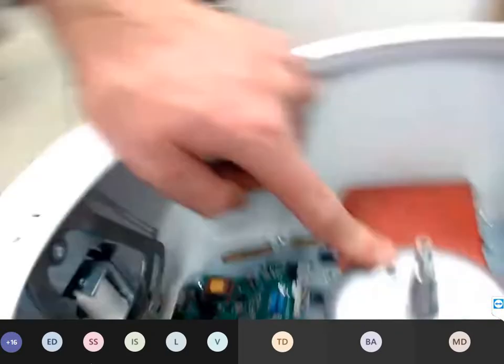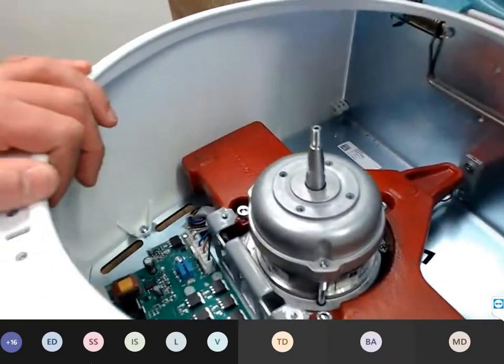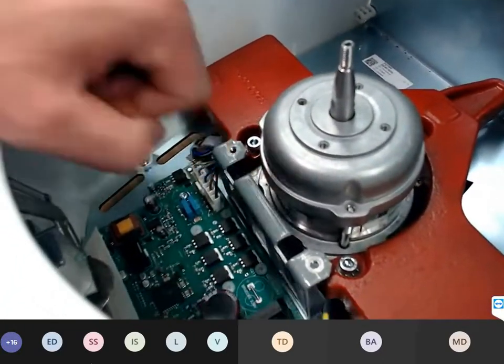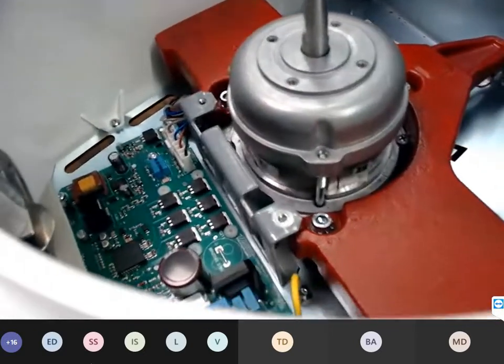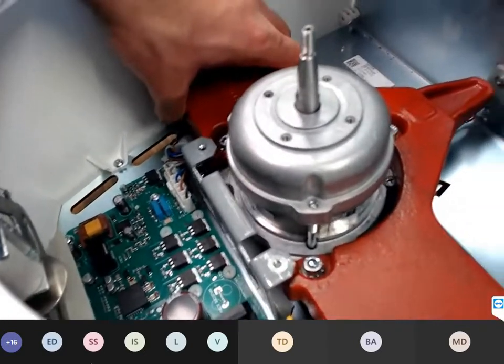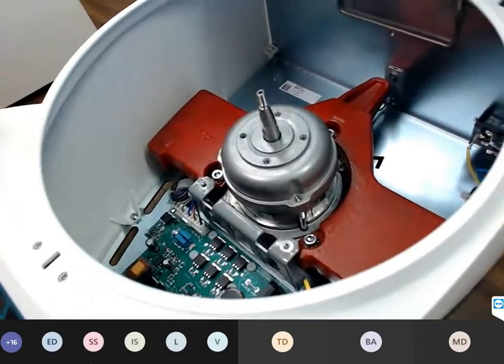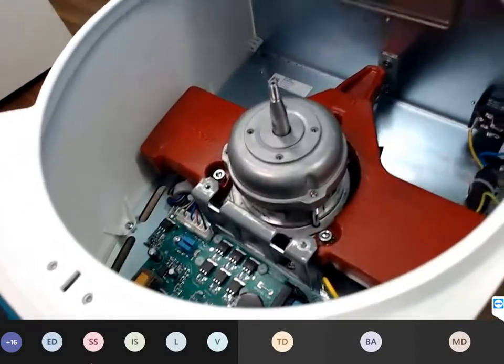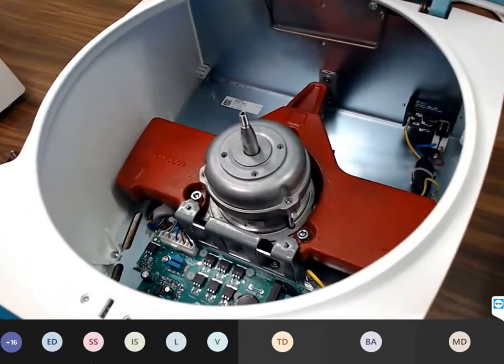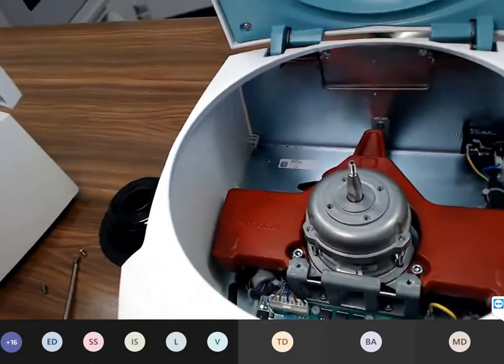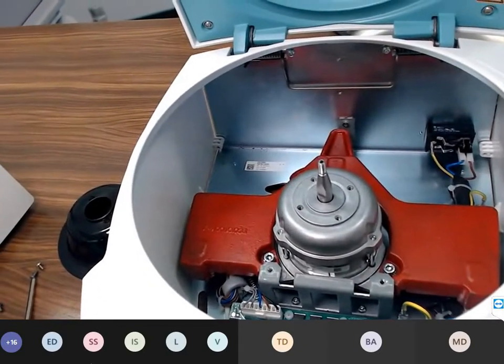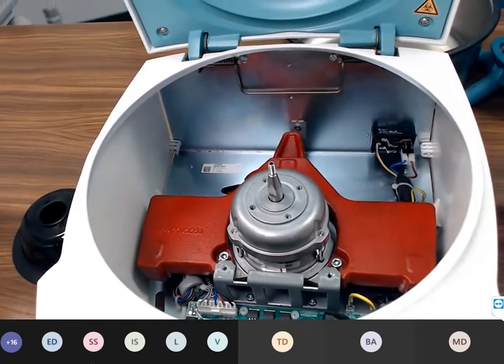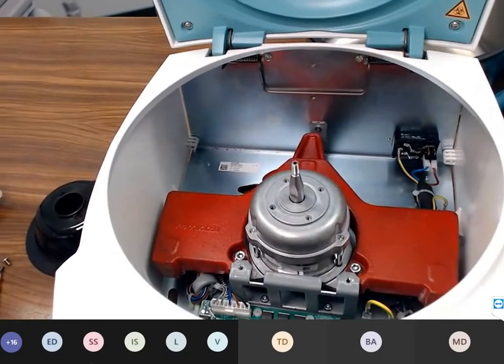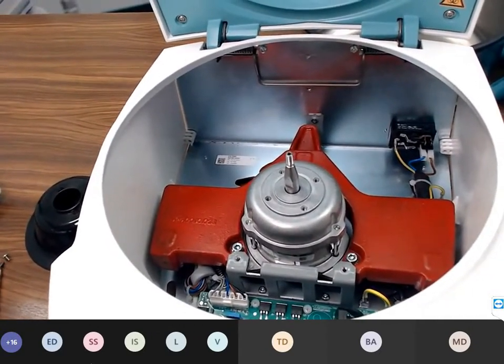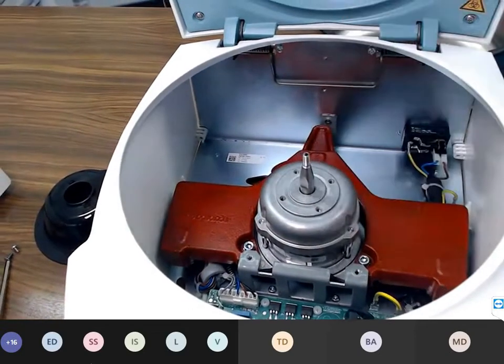So we have here the motor. It has also a nameplate. We have here this red thing at the right for the stabilization of the centrifuge, because we have here a swing out rotor, and with the swing out rotor we have a higher kinetic energy. For the stabilization of the device we need a weight.